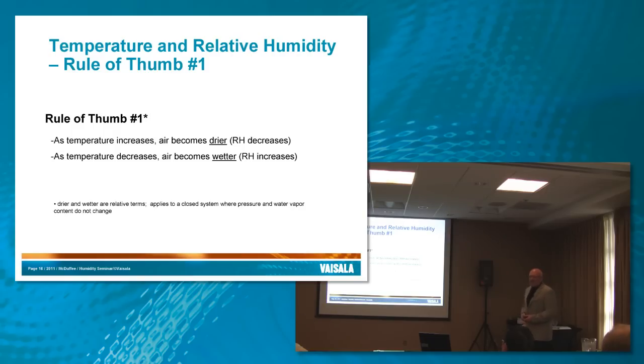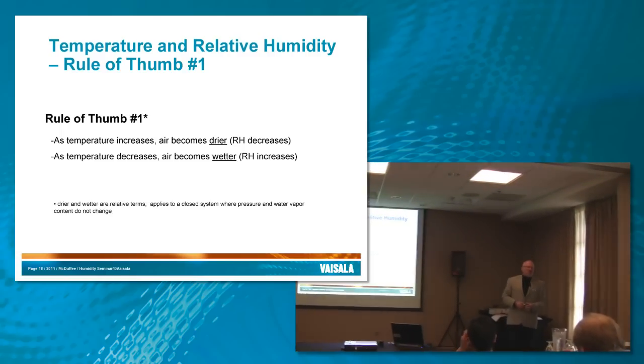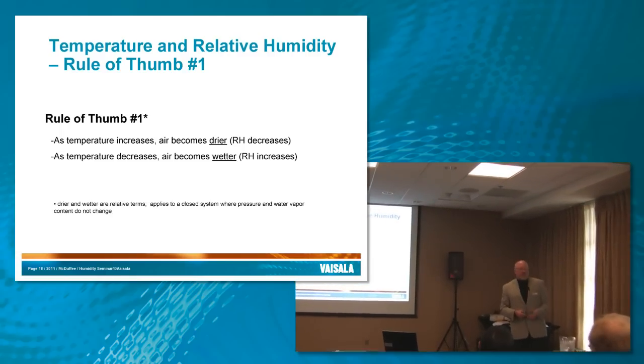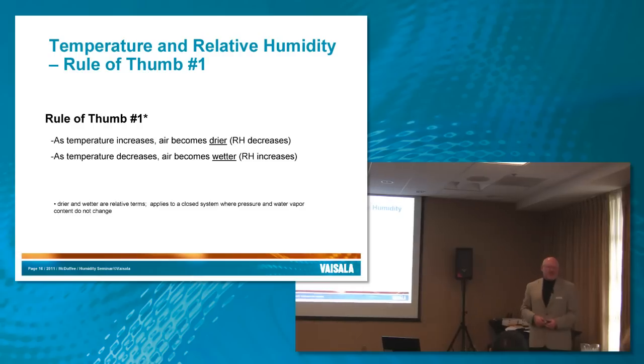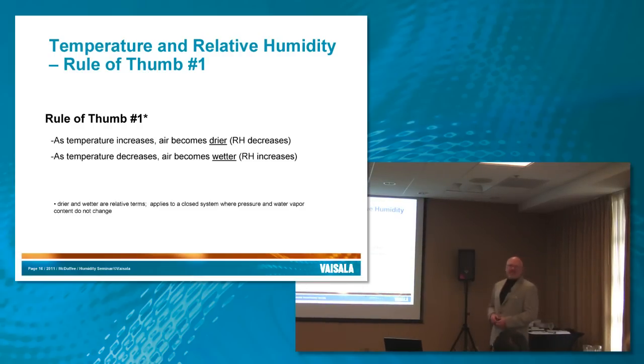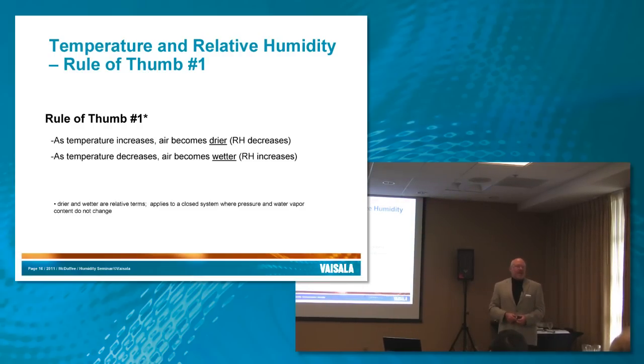A good example of this is in most cities, but I'll give an example of in my office in Louisville. So in the wintertime, the indoor humidity in my office, which, by the way, I can measure because I have instruments in my office. I measure it at sometimes 7%. 7% RH is very dry. But what's happening there, and it happens every place, is in the wintertime, you've got, say, 40 degrees outside. You're at 40% RH. You bring that air in, you heat it up, and obviously you're going to get drier because of this rule.